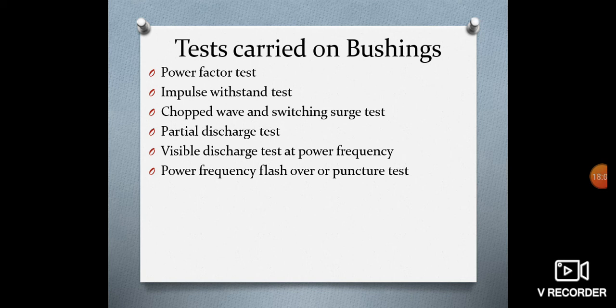Impulse withstand test. The bushing is subjected to impulse waves of either polarity and magnitude as specified in the standard specifications. 5 consecutive full waves of standard waveform 1/50 microseconds are applied, and if 2 of them cause flashover, the bushing is said to be defective. If only one flashover occurs, then 10 additional applications are made. If no flashover occurs, the bushing is said to have passed the test.